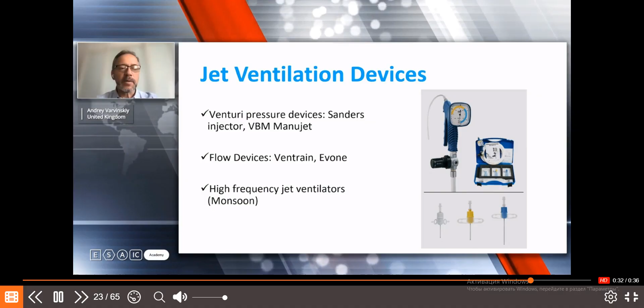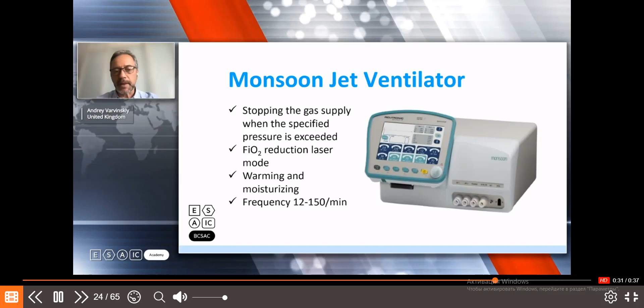This is the Monsoon jet ventilator. It has the ability to stop the gas supply when the specified pressure is exceeded. So it measures the pressure in the airway, and it will cease delivery if that airway pressure is exceeded. It has a function of FiO2 reduction in the laser mode, so when the surgeon says, I'm about to start lasering, you press the button, and from whatever FiO2, it will drop to 21. You could warm and moisturize your gases, and the frequency ranges from 12 to 150 per minute.